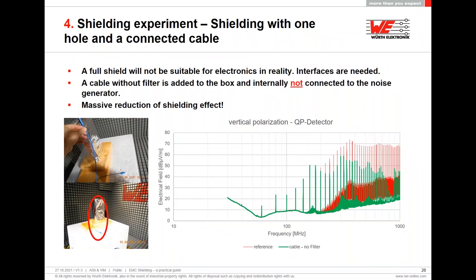Next, we put in a cable — a laboratory 4 mm banana cable. I don't connect it to anything inside; it's just hanging in the shielded enclosure. You can see the noise rises and the shielding is no longer working. Now we have an antenna coming out of the shielded box that is radiating noise from inside. If we add interface cables or power cables to a shielded box, we must add a filter at the point where we enter the shielded box, or use shielded cables that are 360 degrees terminated with the correct geometrical connection.